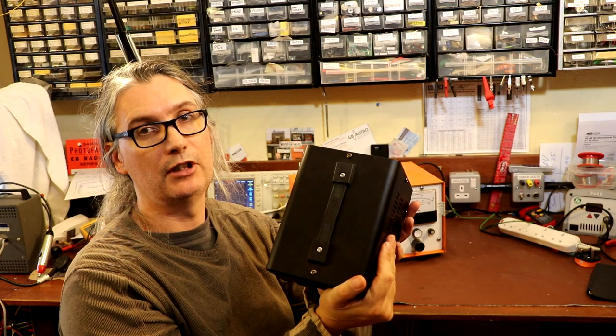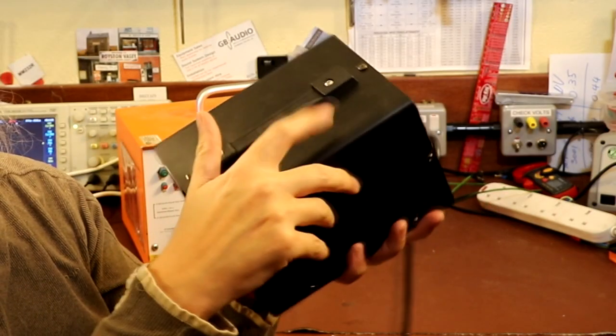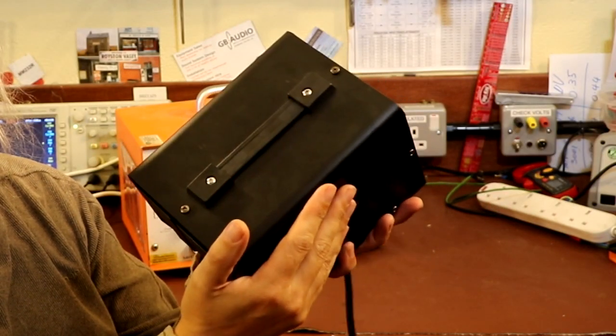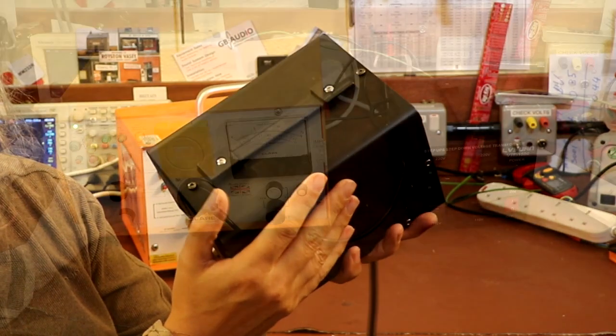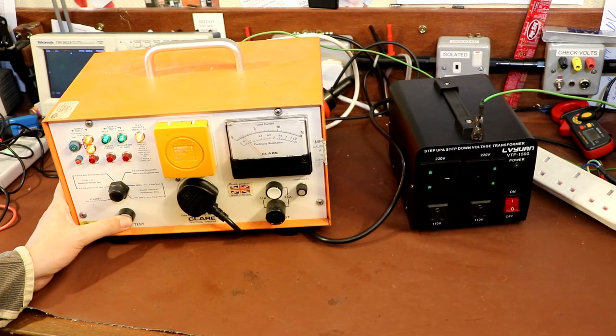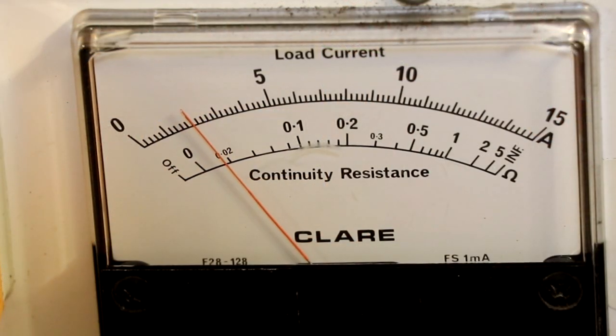Silly mistake. What I will do is, off camera, I'm going to drill a hole in here and fix on a dedicated earthing bolt, and we'll retest it. And that passes absolutely no problem. On the meter here it's displaying our earth continuity, which is less than 0.02 of an ohm, so we have a really good earth connection to the cover of our piece of equipment here.